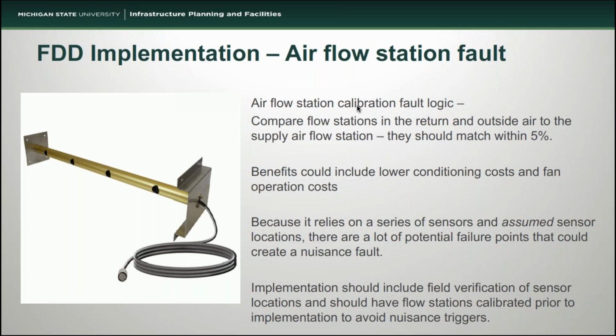There are some downsides to these types of faults, especially as a rule-based fault, because we rely on these sensors' accuracy in order to determine whether or not there's a fault condition. We make an assumption on where the sensor is located, and we also make assumptions on all of the sensors being accurate when we start. So implementation of something like this should really involve verifying those flow sensor locations and changing the fault logic if necessary to accommodate where the sensors are actually located. And then also, really, you need to go through and calibrate the sensors to make sure that you're starting from a known good position when you start to implement this type of fault. Slide.